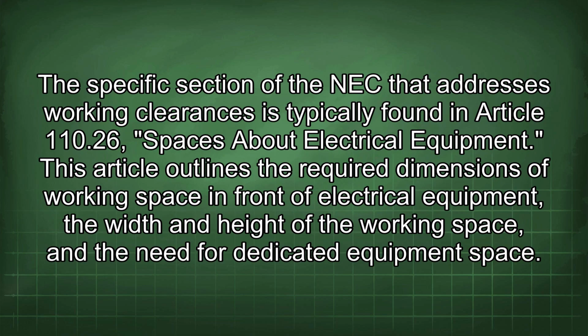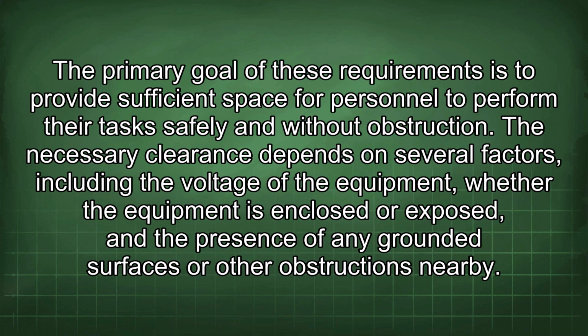The specific section of the NEC that addresses working clearances is typically found in Article 110.26, Spaces about electrical equipment. This article outlines the required dimensions of working space in front of electrical equipment, the width and height of the working space, and the need for dedicated equipment space. The primary goal of these requirements is to provide sufficient space for personnel to perform their tasks safely and without obstruction. The necessary clearance depends on several factors, including the voltage of the equipment, whether the equipment is enclosed or exposed, and the presence of any grounded surfaces or other obstructions nearby.